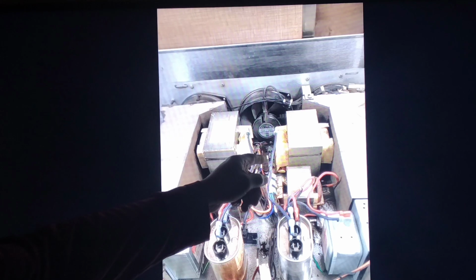You definitely want to make sure your wiring is correct on the transformers, or else that's going to cause problems. It's not that hard because the terminals are numbered on top of the transformer, and each wire has a sticker with T1 dash 1, T1 dash 2, T1 dash 3. It's right up here, 1, 2, and 3. That's how you want to match it up.